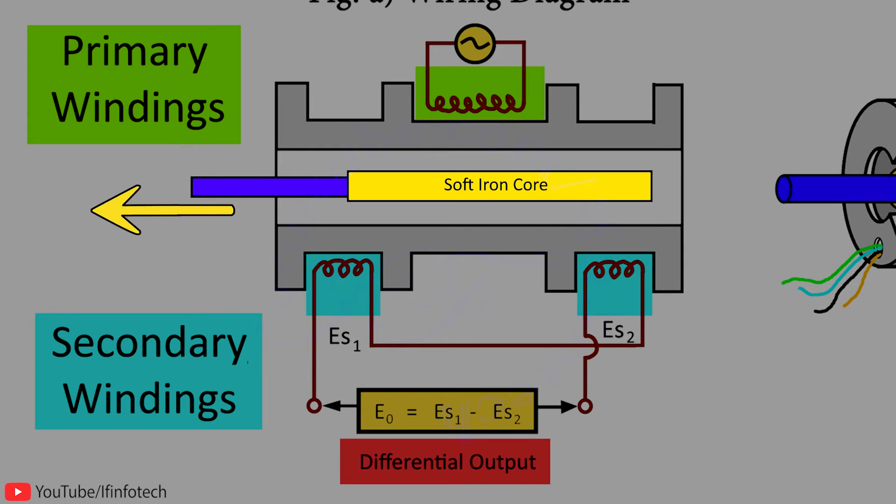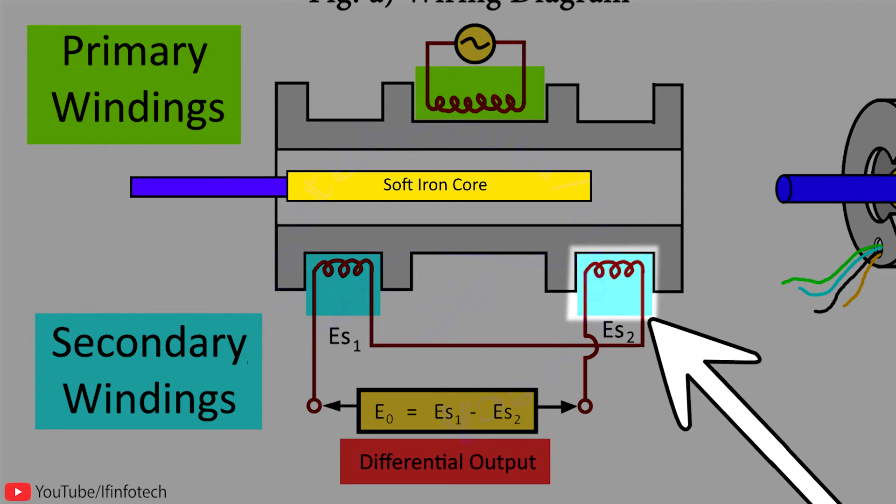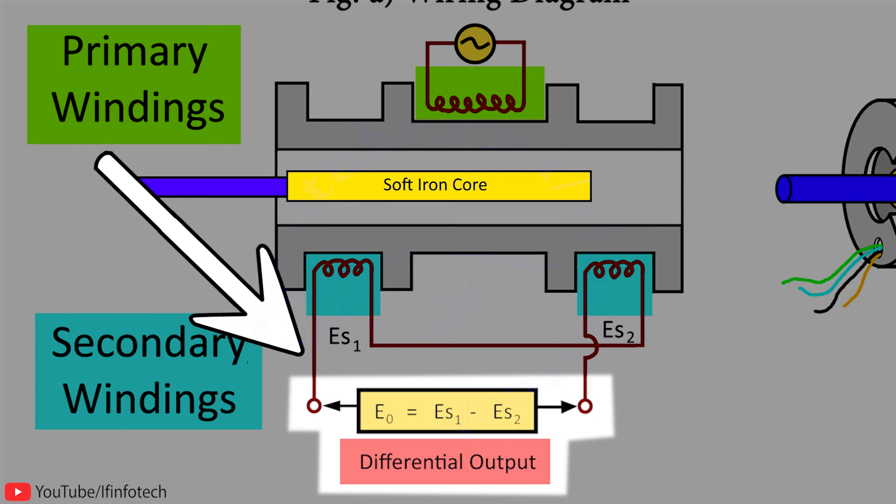When the core is moved towards the left side, then flux linking to coil S1 will increase. At the same time, flux linking to coil S2 decreases. Hence, EMF induced in coil S1 is greater than that of S2. As a result of which, output measured between secondary terminals is in phase with primary voltage.